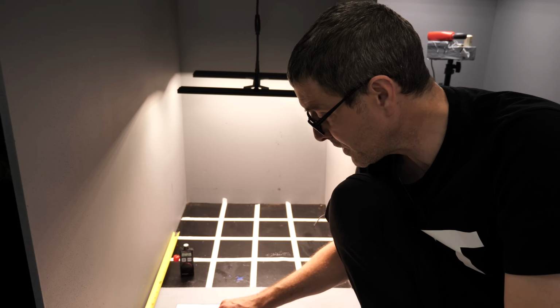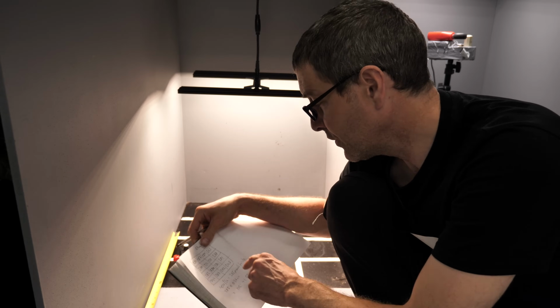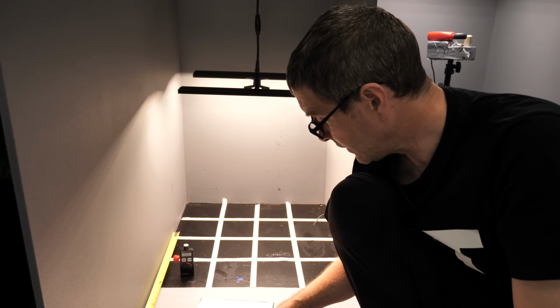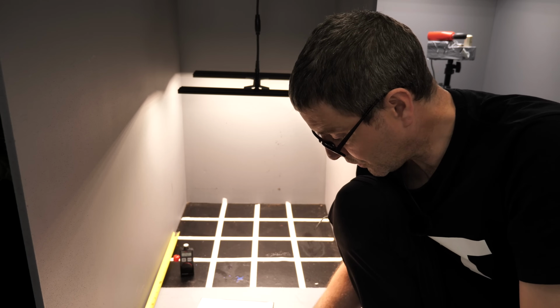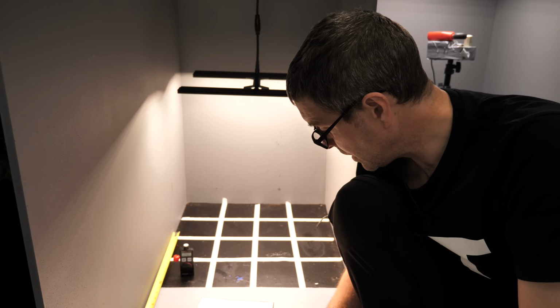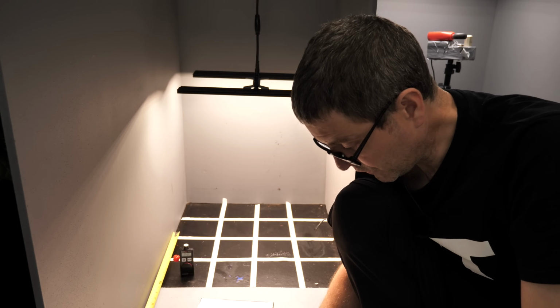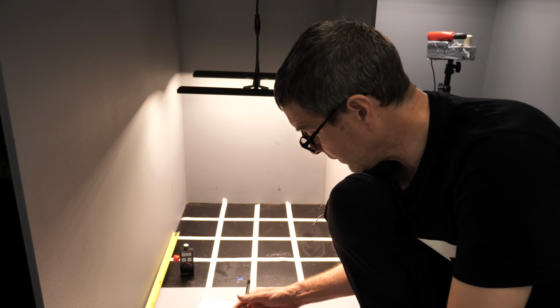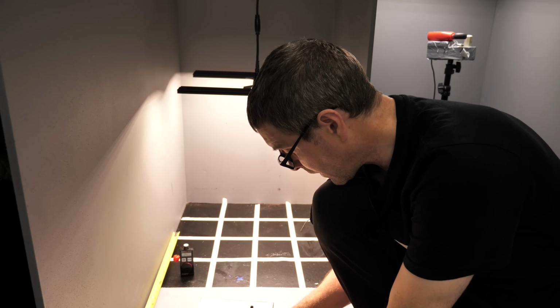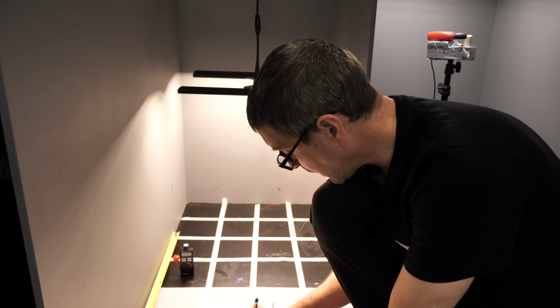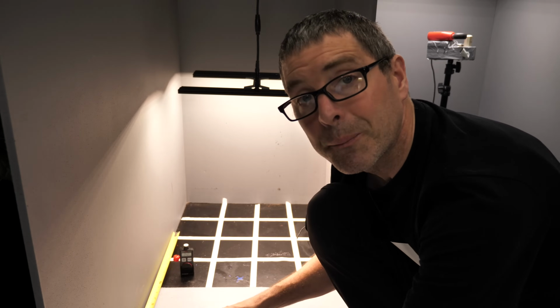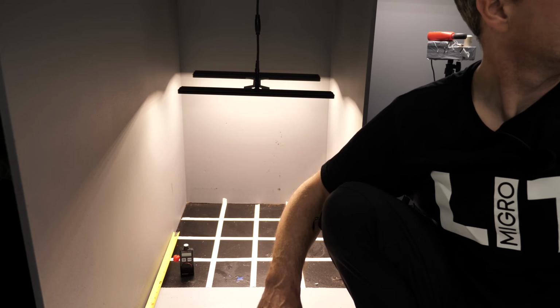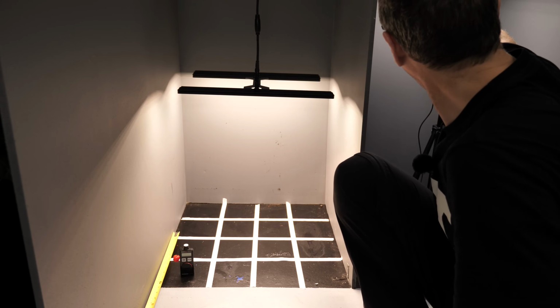And then you've got uniformity, which is the highest over the lowest. So that's 334 divided by 243 is 1.37.